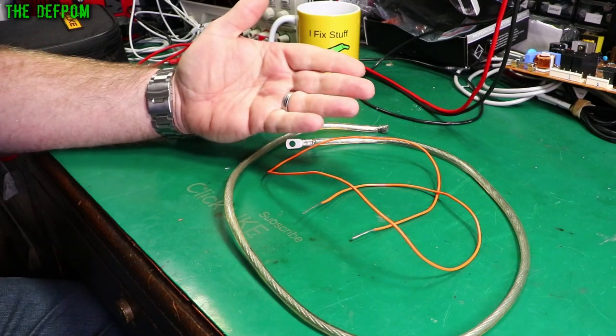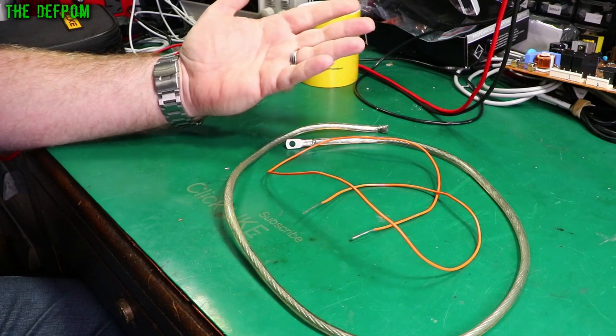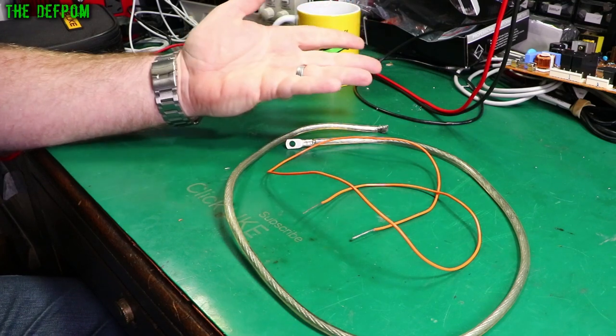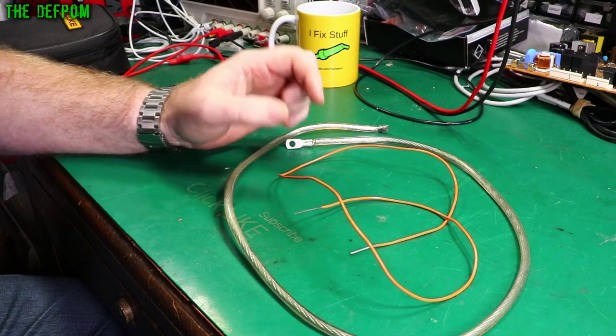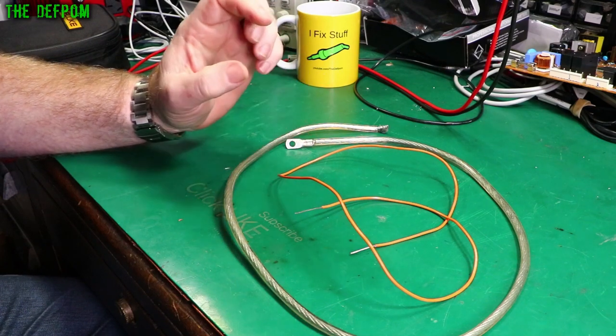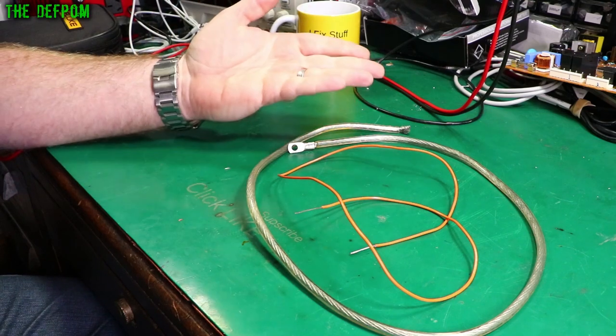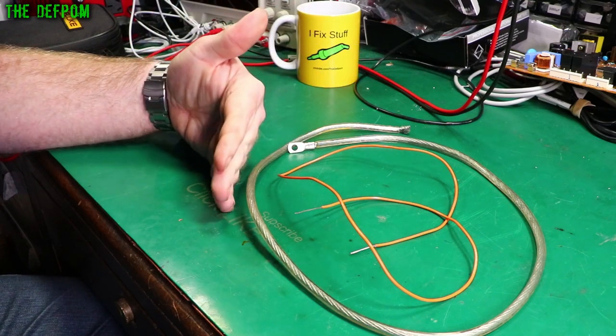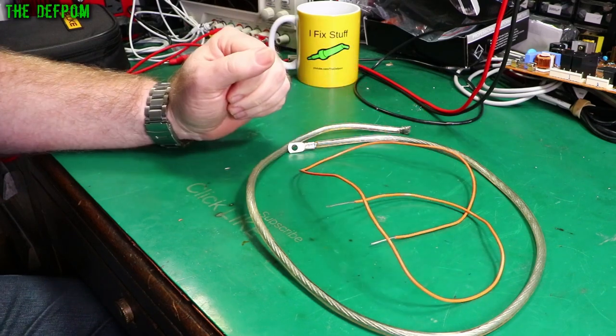In most situations you probably won't care, but sometimes you do care about the voltage drop. This is another reason why lines companies use really high voltages such as 33,000 volts or 110,000 volts. Because for the same power the current is lower. That means less losses. Because it's the current through the cross-sectional area which determines your losses. If you're using a higher voltage you've got less current. Less current means less power dissipation in the cable.